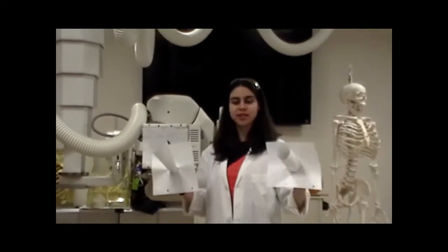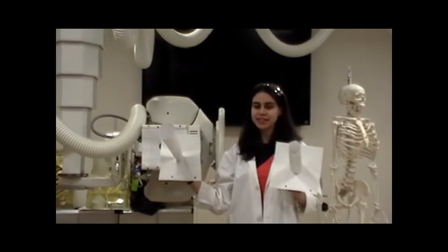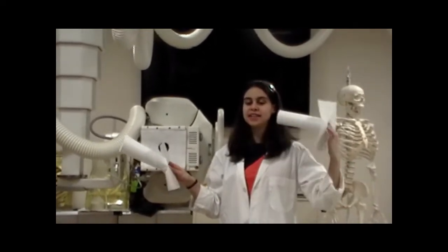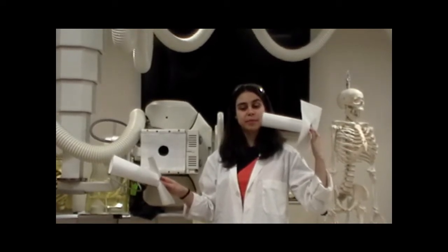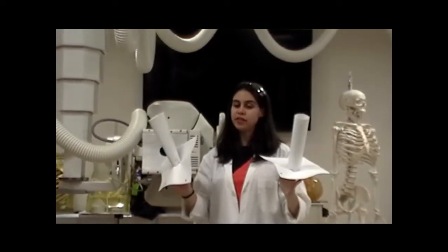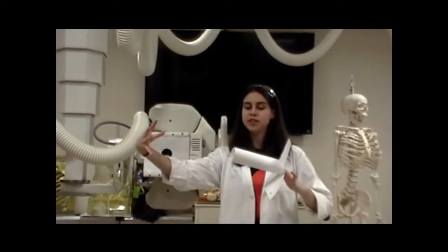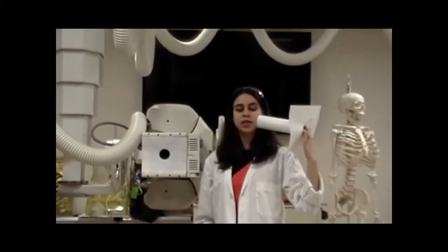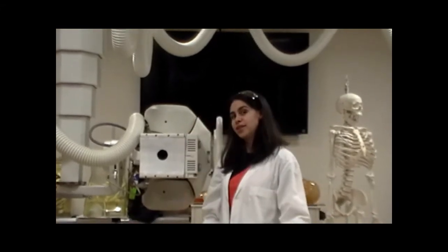Another beam restrictor you can use is a lead cone or cylinder that both attach to the tube housing. Both have an extended flange that can be telescopic. By getting the end as close to the patient as possible, you can limit the penumbra. The cylinder is better than the cone as it allows for less beam divergence. The cylinder is often used in a dentist's office to see the teeth or to better see the sinuses in a more medical setting. Finally, collimators.